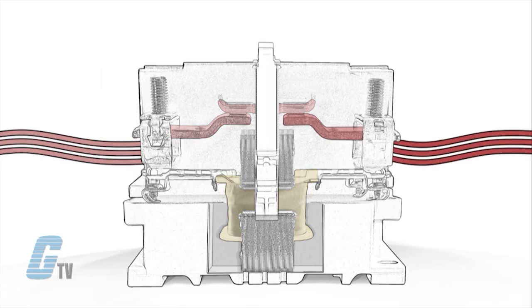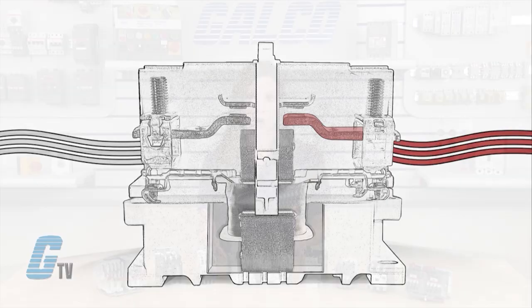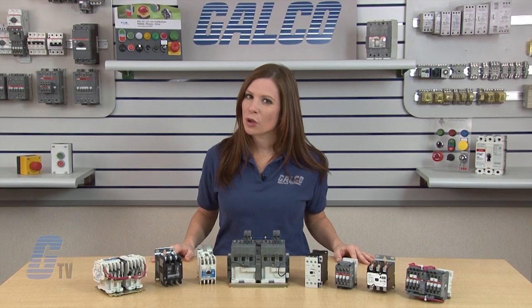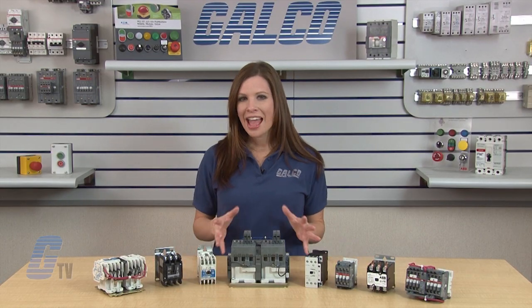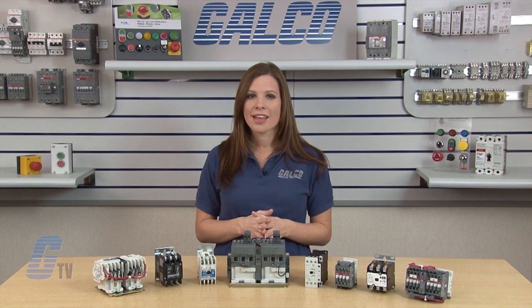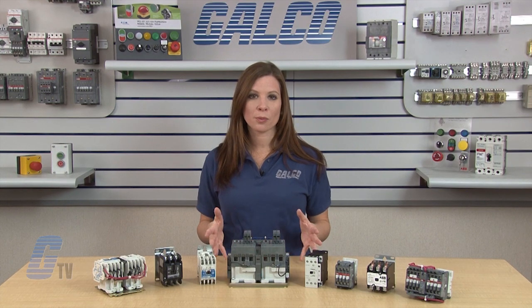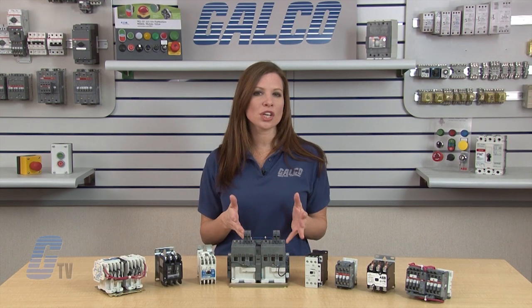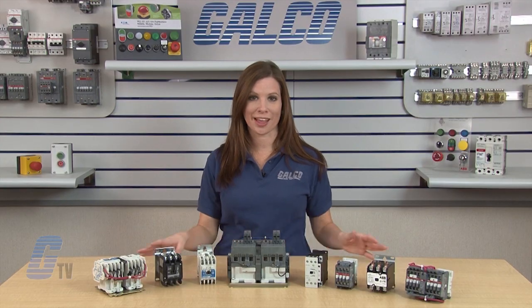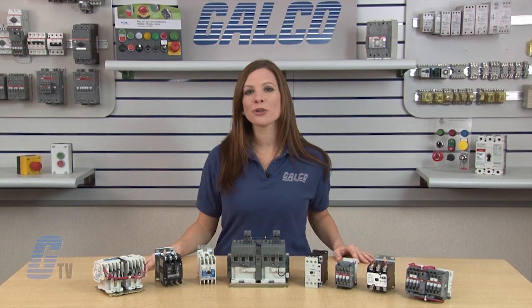When the coil is de-energized, the magnetic field is broken and the spring forces the two sets of contacts apart. Contactors are used when no overload protection is necessary and at lower levels of electrical current. They are also operated electromechanically and use a small control current to open and close the circuit.